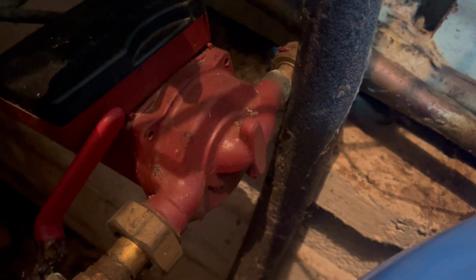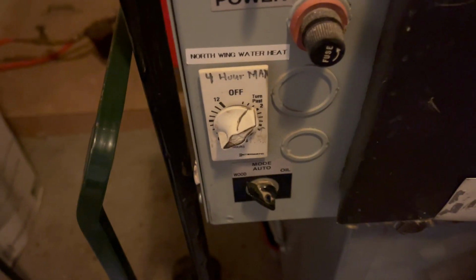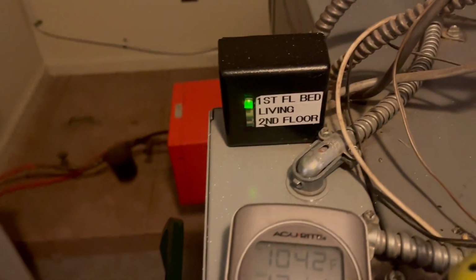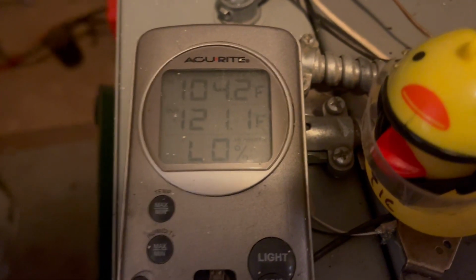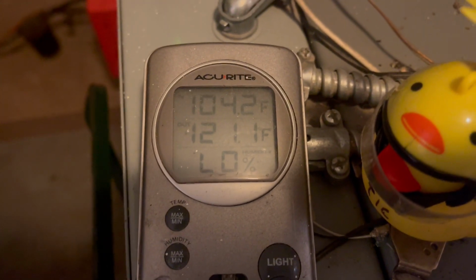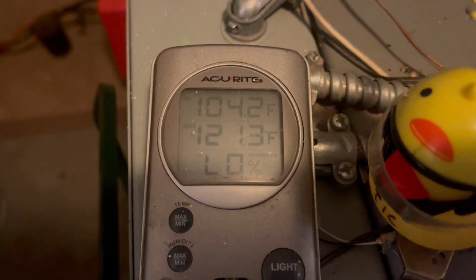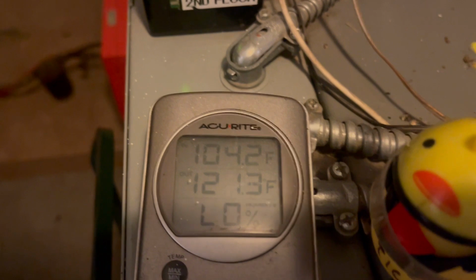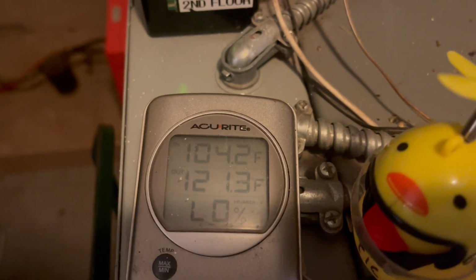And my timer on the boiler turns this pump on whenever I want to heat the water in this massive 80-gallon copper jacketed hot water heater that was installed in 1950 and is still functioning today. This timer turns on the pump you just saw and forces the circulating pump on, just in case no zones were asking for heat. This thermometer has been rigged so that it's showing the temperature coming into the heat exchanger and out of the heat exchanger. Into the heat exchanger also represents, that's the top number, the temperature that you would feel if you were to begin using hot water in the north wing of the house.